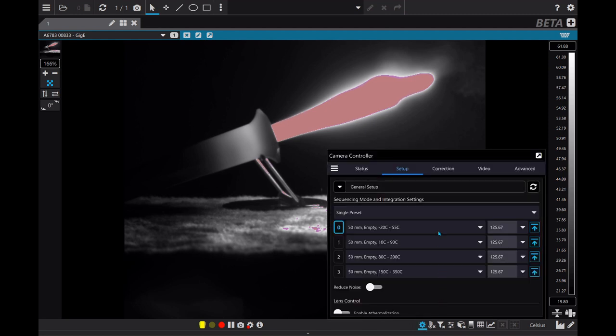In the camera controller, you can see the temperature ranges that the camera is currently calibrated for. We have a -20°C to 55°C, a 10°C to 90°C, 80 to 200, and 150 to 350°C. Currently, we're only looking at the target with a single calibration range. That's the -20 to 55°C.